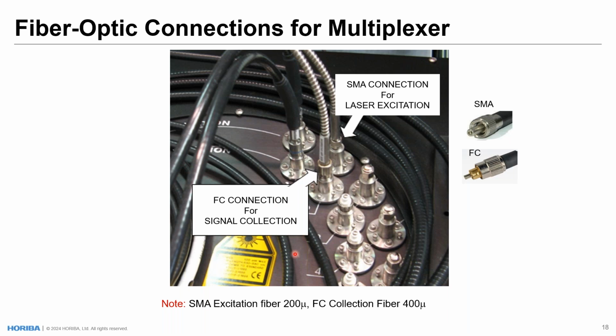We'd also like to point out here that these are quite large diameters for these fiber optic cables. We do this because the larger the collection fiber, for example, the more efficient signal collection we can achieve at the sampling site, which results in better signal to noise collection for the analyzer, which goes hand in hand with the low detection limit that our analyzers provide.